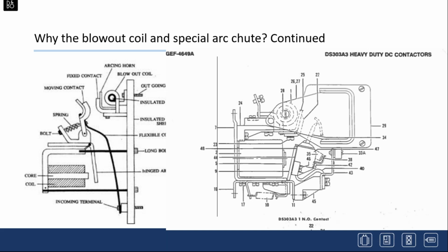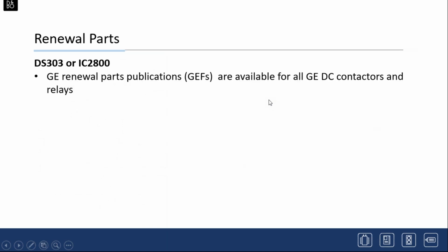Again, to go into that same picture we talked about before, the DC contactor with the blowout coil, the stationary and movable tips. This configuration is the old IC2800 version. This is what the DC contactor looks like, the DS303, again with the operating coil, movable and stationary tips. You have your blowout coil here, and this is the arc chute that totally contains the arc. So this is the earlier version, the IC2800, and this is the DS303 version.